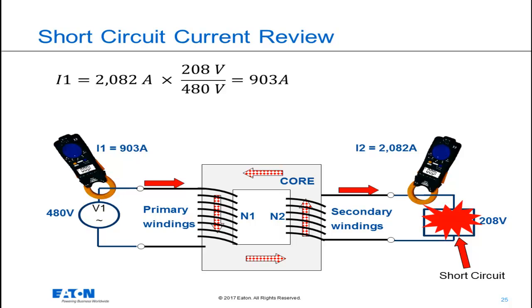From a selective coordination perspective, during a fault, the overcurrent protective device on the secondary would see 2082 amps, and the overcurrent protective device on the primary would only see 903 amps during this short-circuit event.